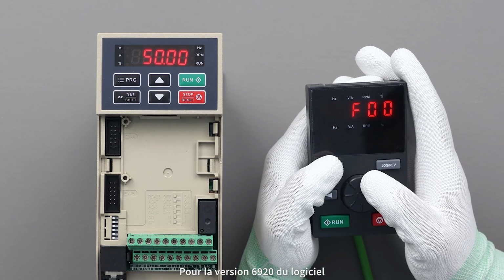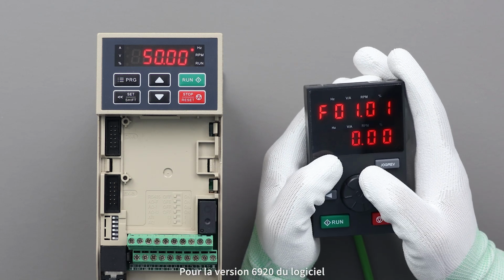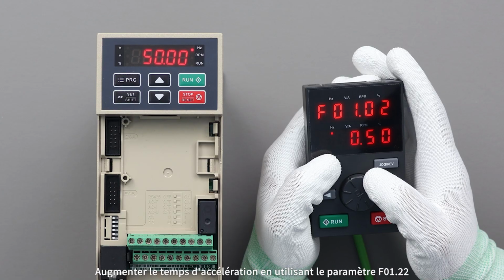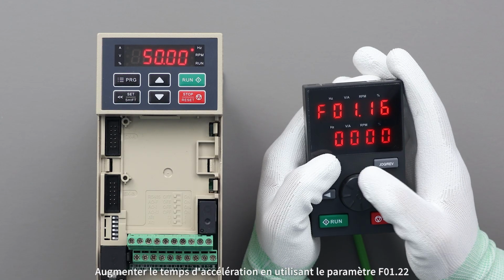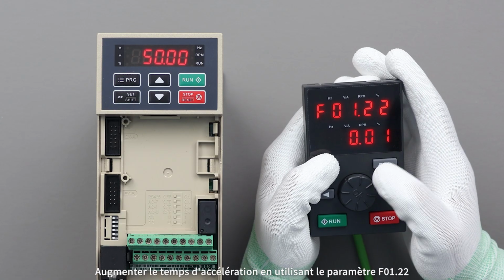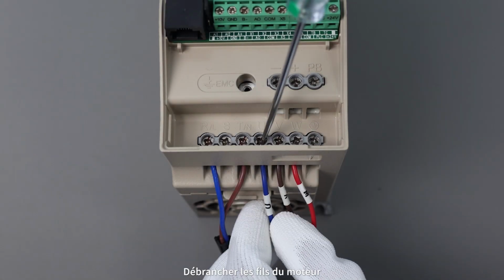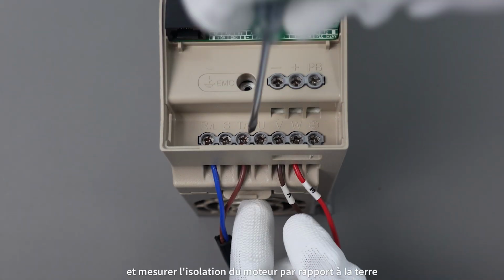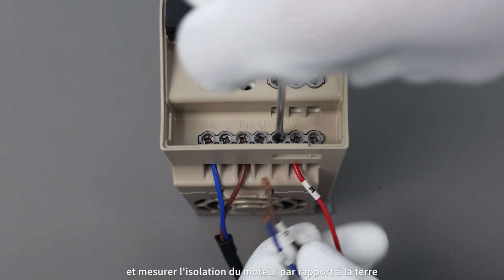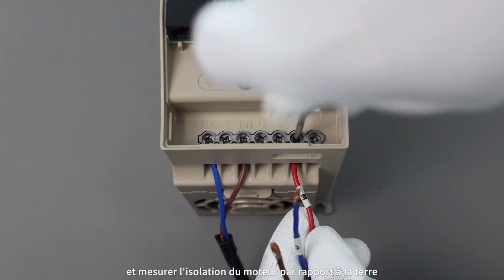For software version 6920, increase the acceleration time using parameter F01.22. Test motor insulation. Disconnect the motor wires and measure the insulation of the motor to the ground.